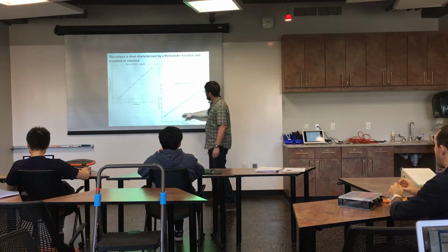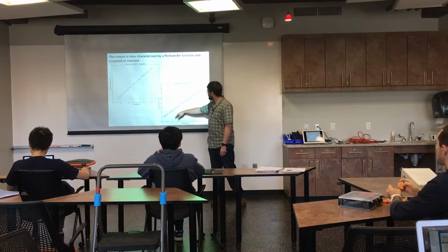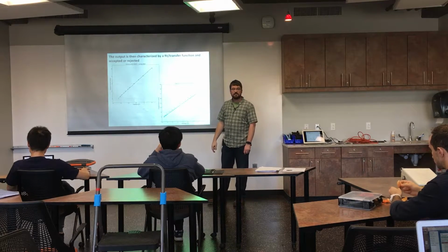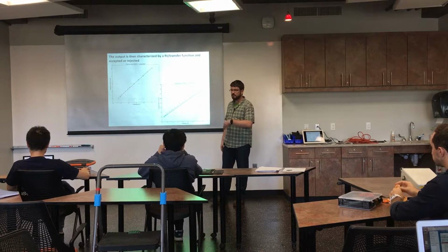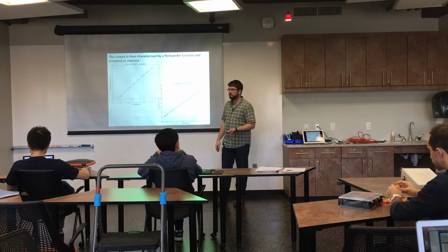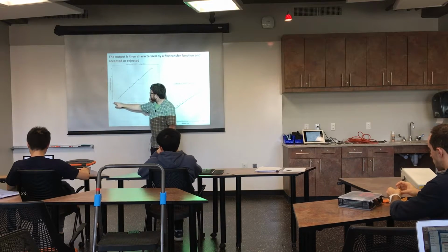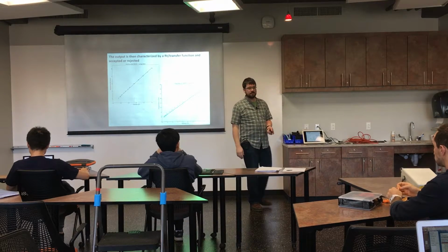This transducer had some issues, right? The slope looks similar, but there's some hysteresis in this curve, where we went up and then we came back down, and we got some slightly different readings. So this calibration would need to be redone, and if you get the same result again, then there's probably something wrong with the transducer. Whereas here, when we went out and back down in displacement, the dots are pretty much exactly on top of each other. You can't even see them.